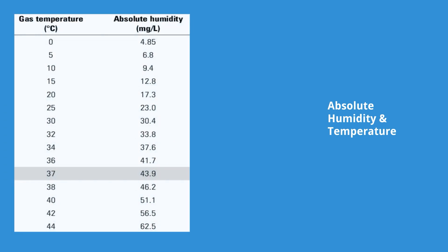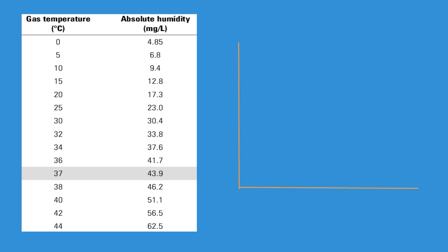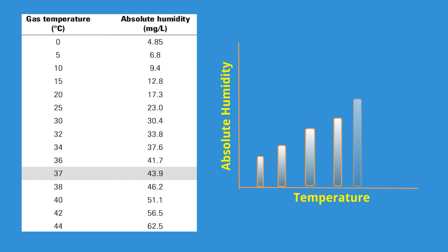Although we don't specify temperature in the definition, there is a relationship between gas temperature and absolute humidity. From a table, at 0 degrees centigrade the absolute humidity is 4.85 milligrams per liter, at normal body temperature of 37 degrees centigrade it is 43.9 milligrams per liter, and at an extreme condition of 44 degrees centigrade it is 62.5 milligrams per liter. A graph of gas temperature versus absolute humidity shows that absolute humidity gradually increases with temperature.